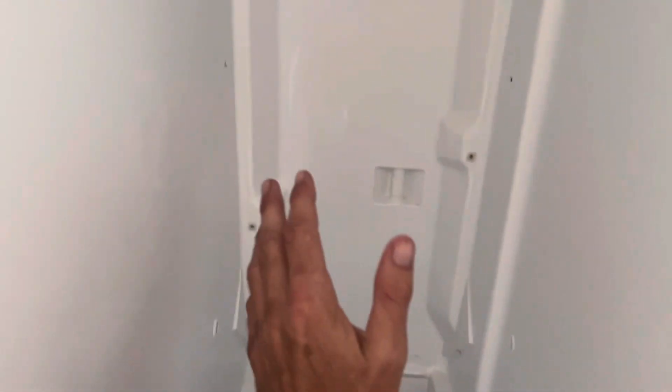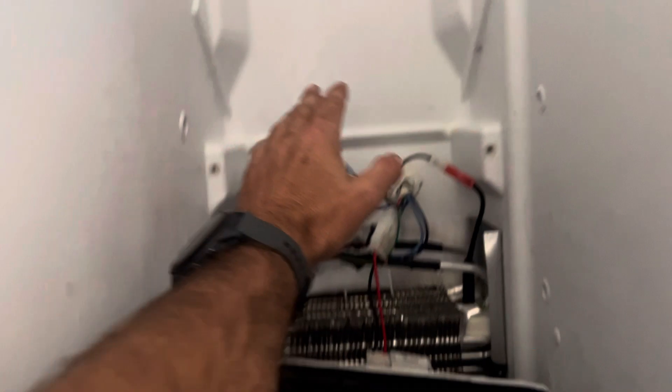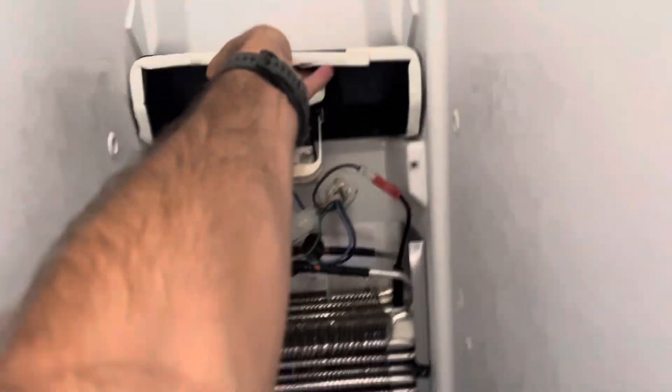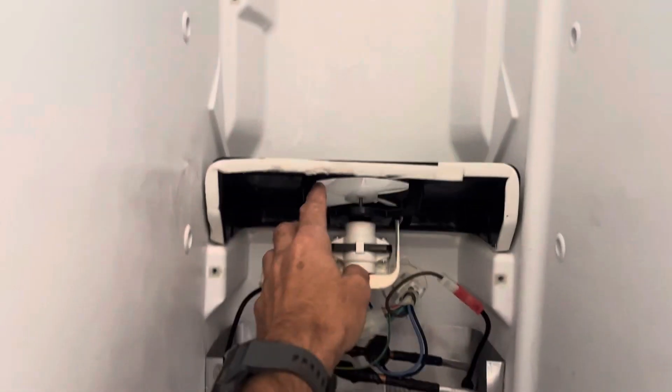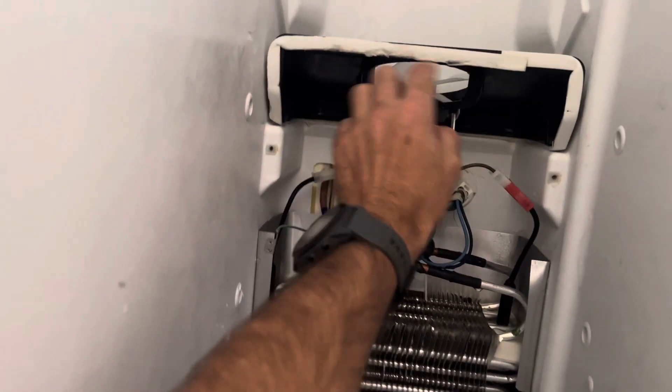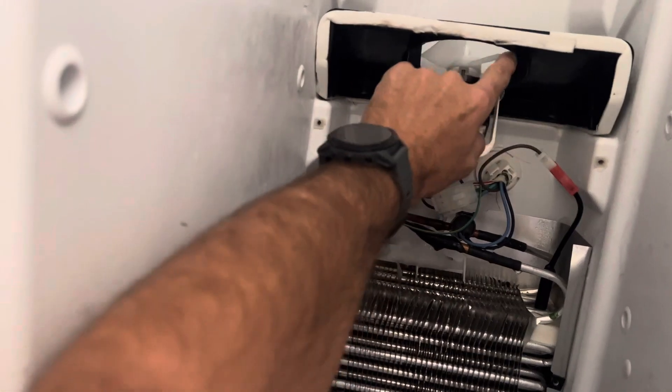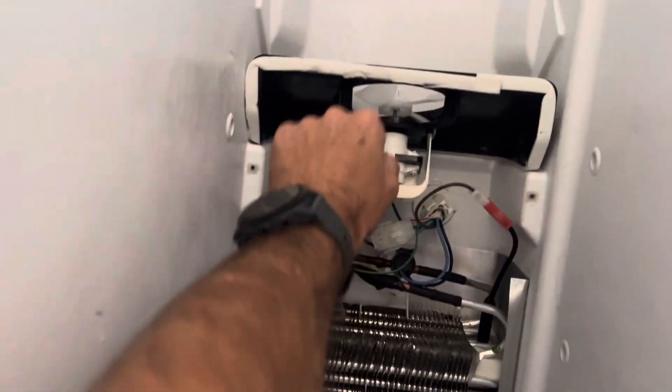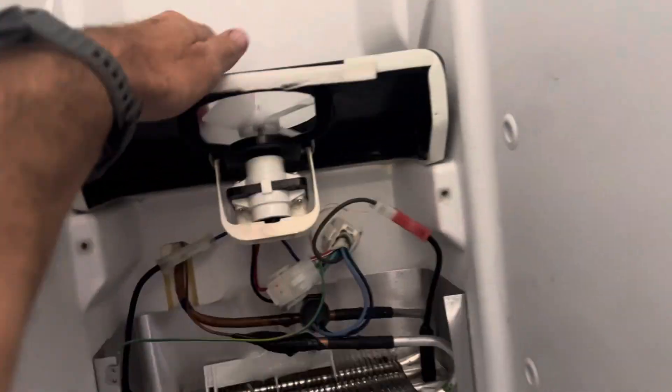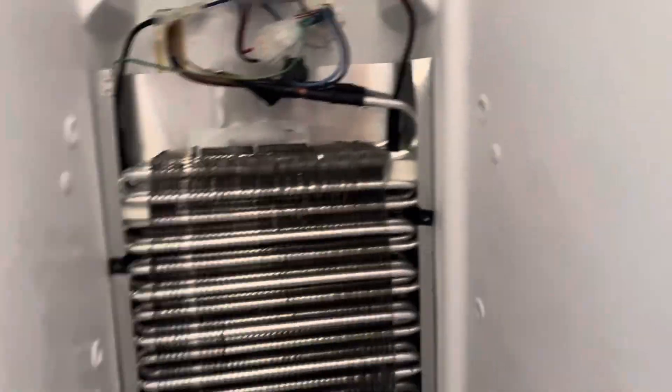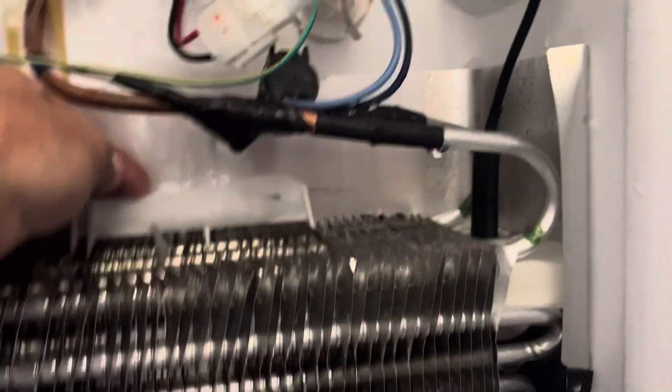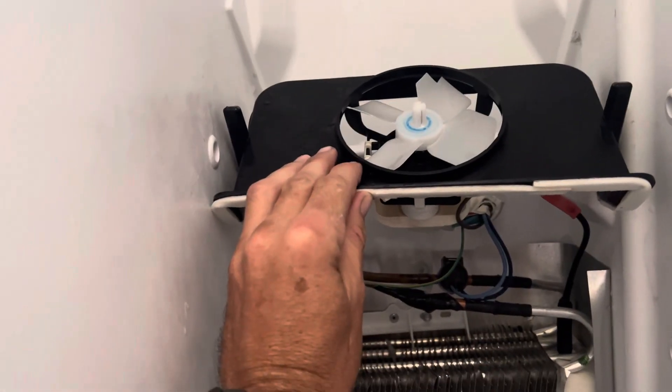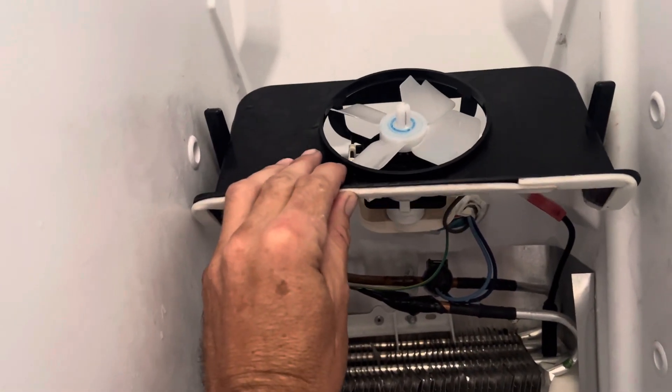I've already removed a bunch of stuff. Once it freezes up, it eventually blocks the fan. Before you know it, you hear this loud vibrating noise because the ice is blocking the fan. You can still see some of the ice right back here.